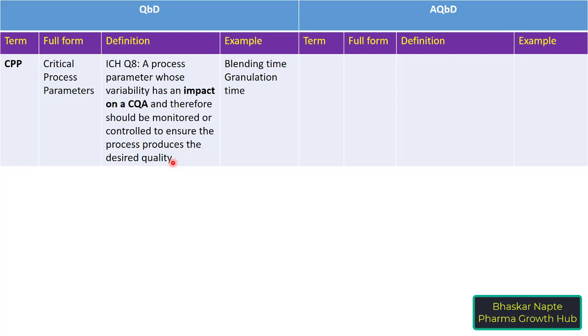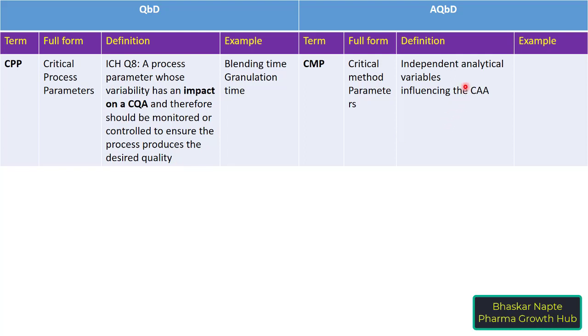The equivalent term in AQBD for CPP is CMP, or Critical Method Parameters. These are independent analytical variables influencing the critical analytical attributes such as retention time and resolution. Examples of critical method parameters include mobile phase composition, pH of the mobile phase, buffer strength, flow rate, and injection volume — all of which can certainly influence the CAA.